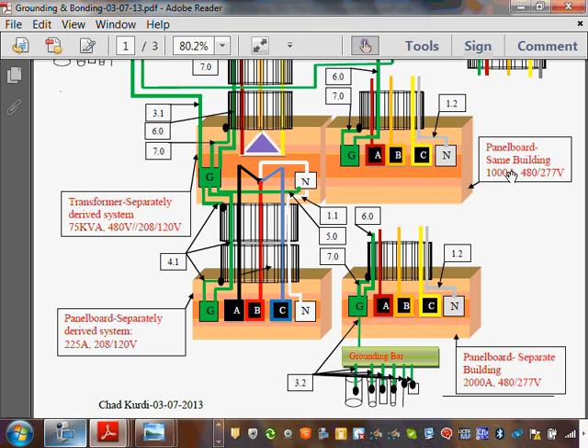So they've changed the way you have to do that on farms versus what they did a number of years ago. Well, it used to be they allowed you to bond a neutral at the second building. That's a change, yes. So in a case like this, it will save you 1 conductor to save money. Then you don't have to put an equipment grounding conductor here. Your neutral will be bonded here, and still acts as a way for existing building. An exception for existing building where you don't put an equipment grounding conductor.